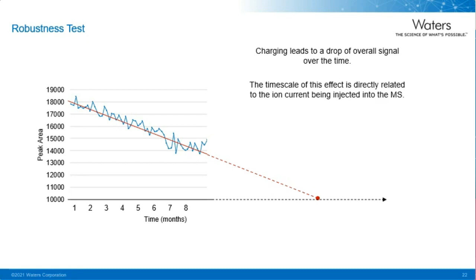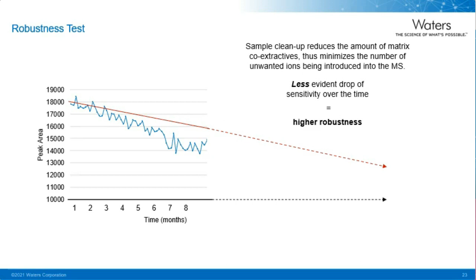When injecting samples processed by a simple dilute and shoot approach, we might find this trend. If we consider a drop to 10,000 counts as the unacceptable limit at which some intervention is needed, we can work out the time at which we need to intervene with some maintenance, such as cleaning of the cone, StepWave, PM, and so on. However, when we do some cleanup, like an SPE pass-through, we might experience a higher robustness of the method, which ultimately decreases the rate at which the instrument is losing sensitivity because we are introducing less unwanted material. As a result, the system will require less maintenance and can work for longer periods of time.